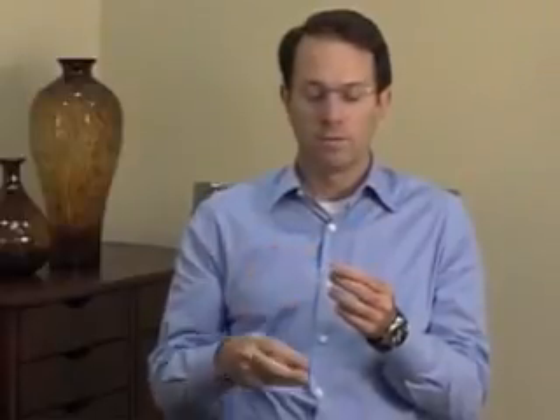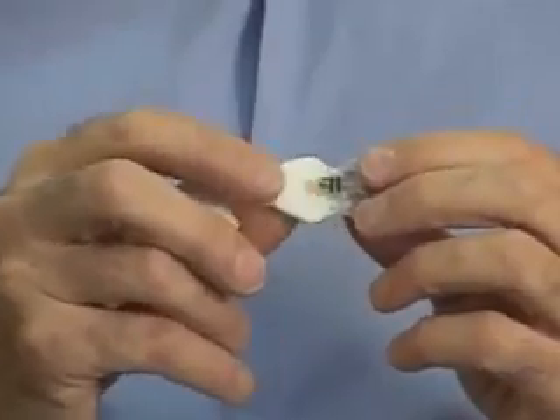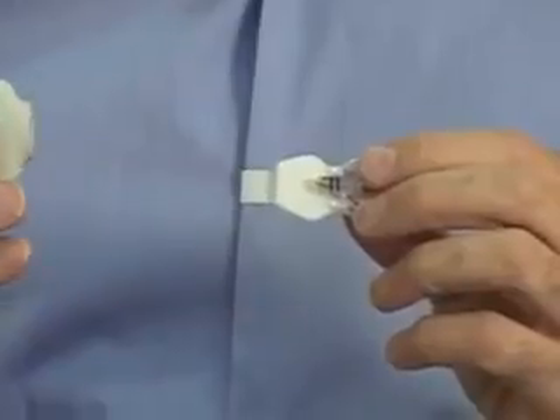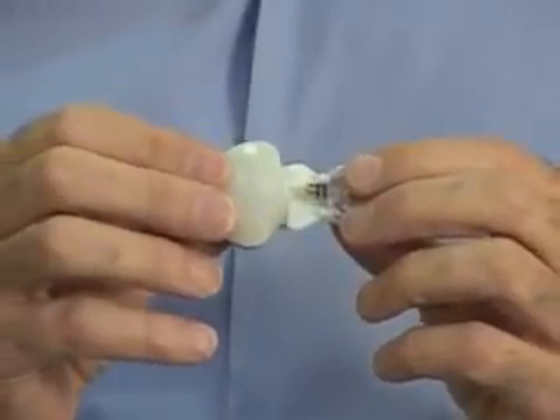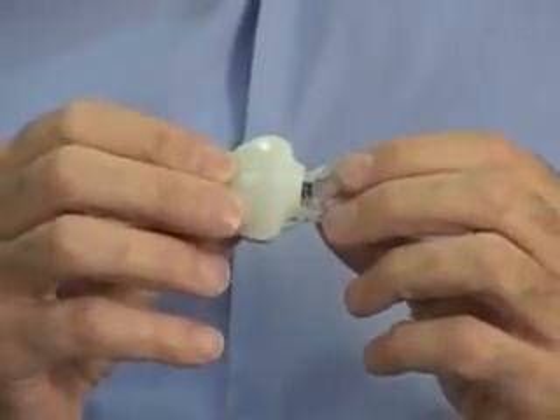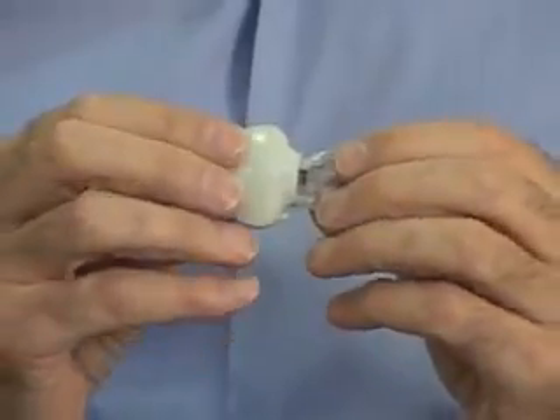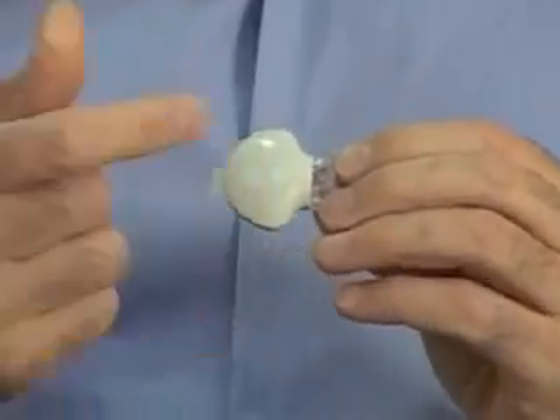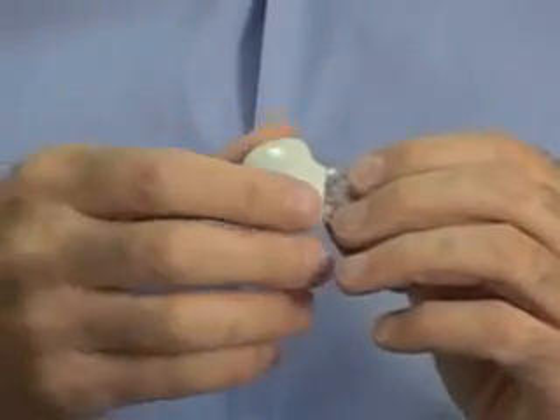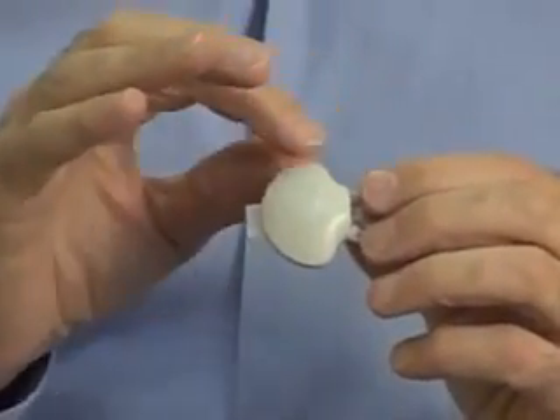So once the glucose sensor is placed underneath the skin of the person, it has to be connected to the transmitter device, the MiniLink, and that connection process occurs. And once that happens, the sensor is physically connected to the transmitter. Inside this device are the electronics that operate the sensor and measure the signal created by detecting glucose in the body. And then there's a transmitting element which transmits the data every 5 minutes to our pump or the Guardian monitor.